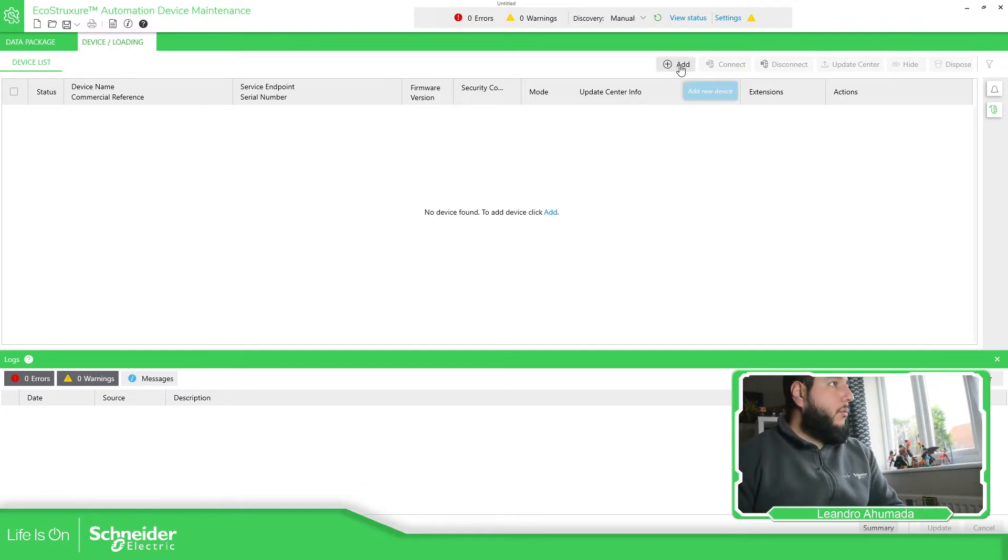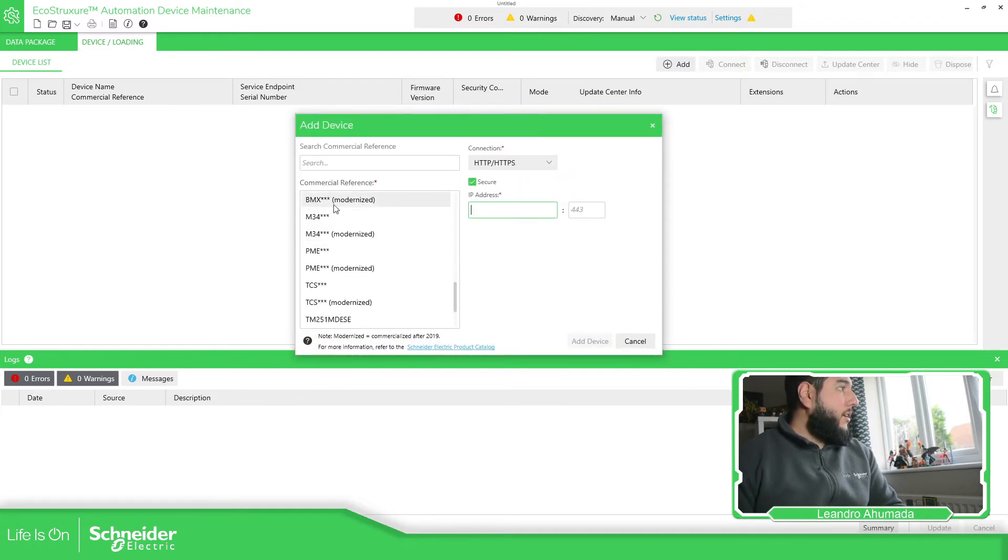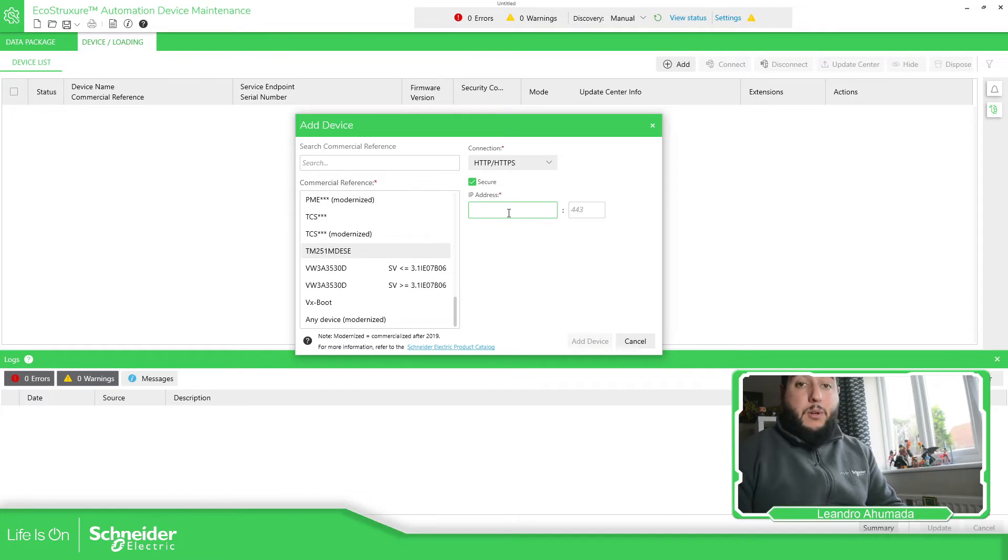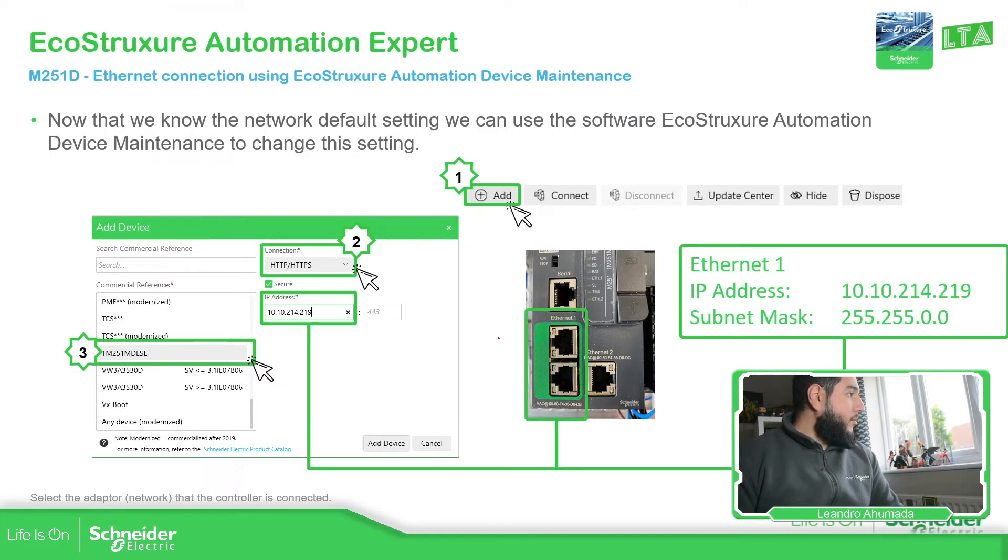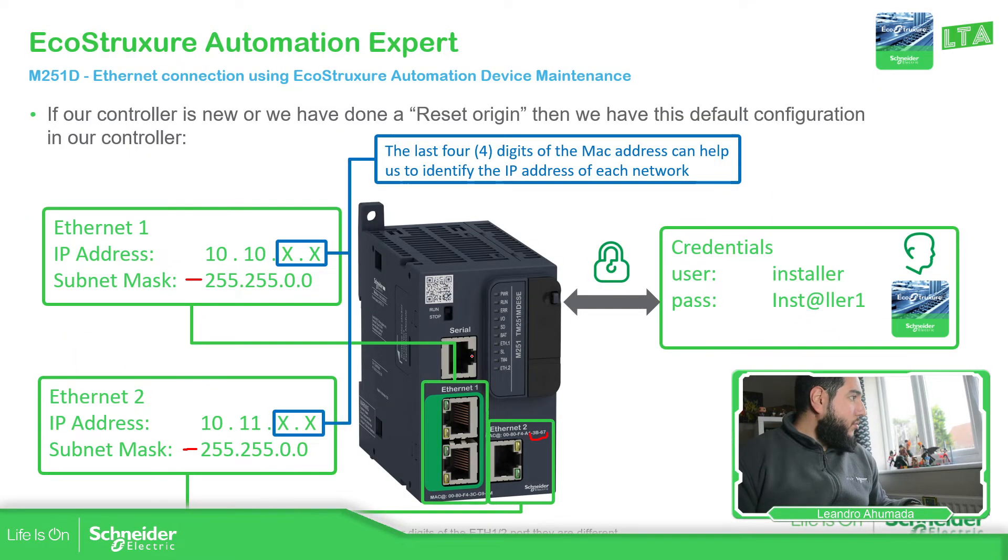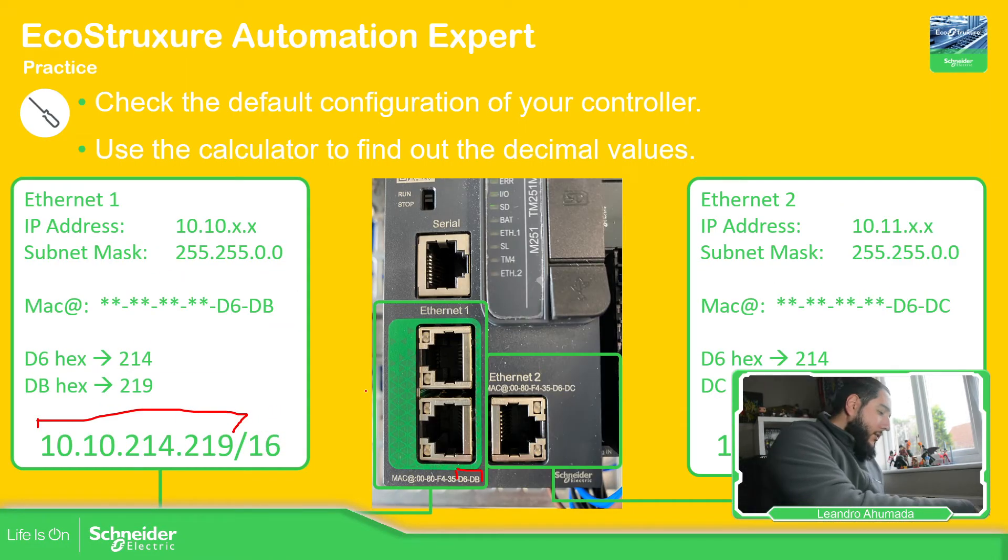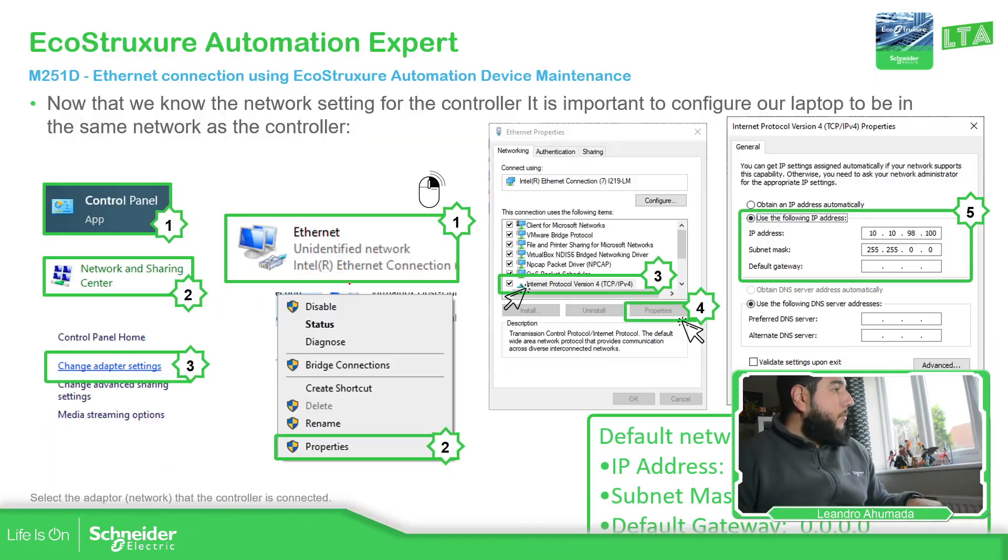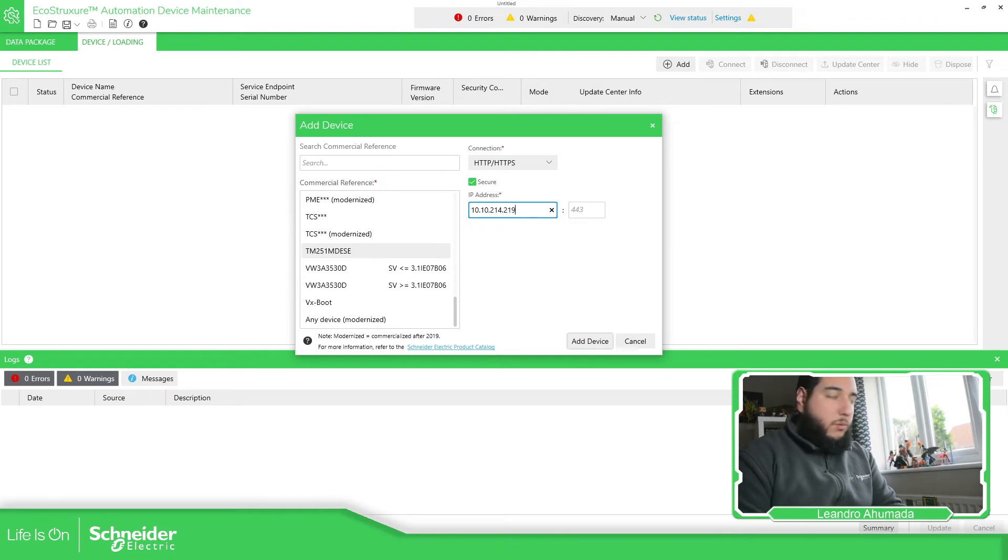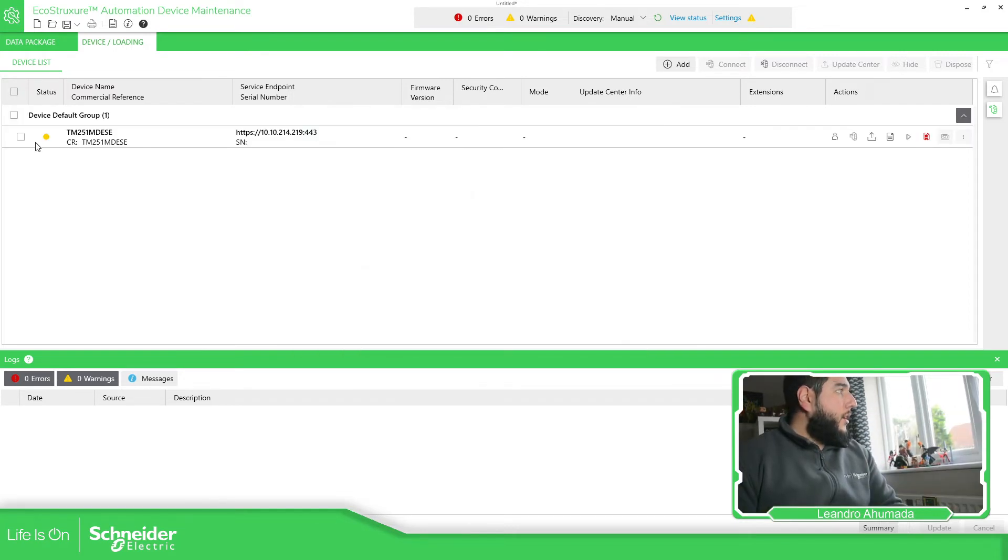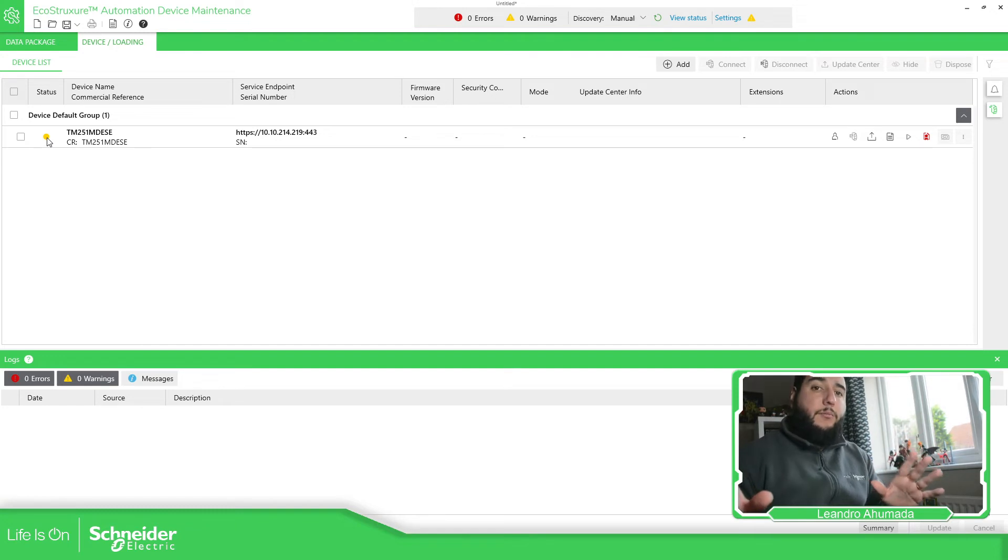So what we can do is to add the equipment. So if we press the add button over here, we just need to find here the commercial reference, which is this one, TM251MDESE. And here we just need to type the IP address. In our case, the IP address was 10.10, I don't remember. Let me just write it down. It was this one. I don't forget 10.10.214.219. So don't need to put anything over here to just add the device. And here you can see that the status, the device is reachable. So it's the case. I can see the device is in there.